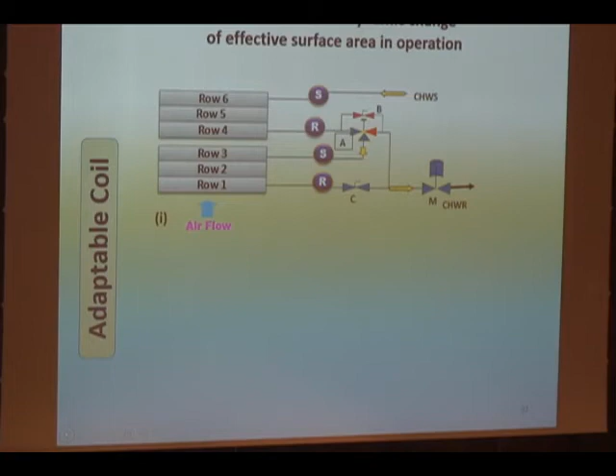If we had the 200 kilowatts load as per design, you have it at installation, at commissioning, no problem. The consultant is happy, everybody is happy if we had the load. But the problem is, the load at installation is not 200, but 100. You need a smaller coil. What can you do? We can do something like this, where we make the large coil become smaller.